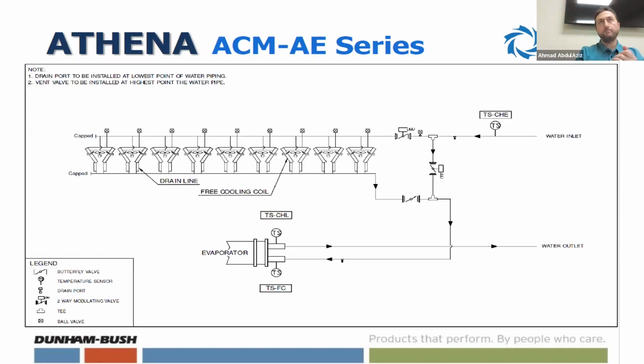It will be 10-15% load, and it can reach 100% load. Now, it goes by EC fan based on the pressure. One of the questions was about what will happen with dirty condenser coils. Based on your pressure, the EC fans will work at high speed or lower speed, because it's ECM. It's like from 0 to 10, so infinite steps of speed. Once it reaches the lower pressure set point, it gives a command to the compressors to switch on or off based on your ambient and your design.